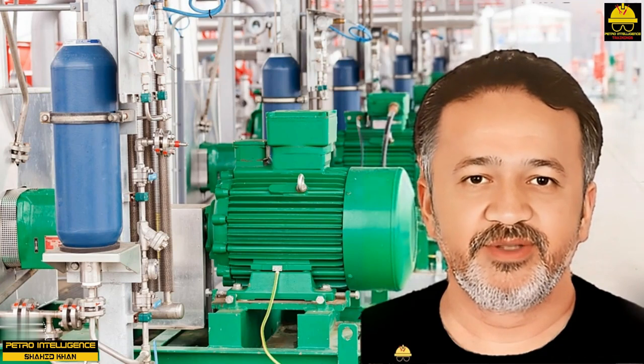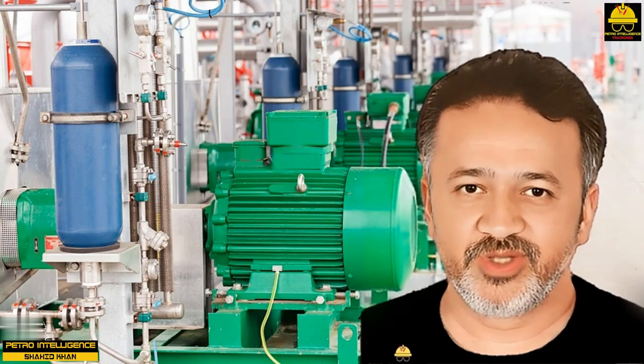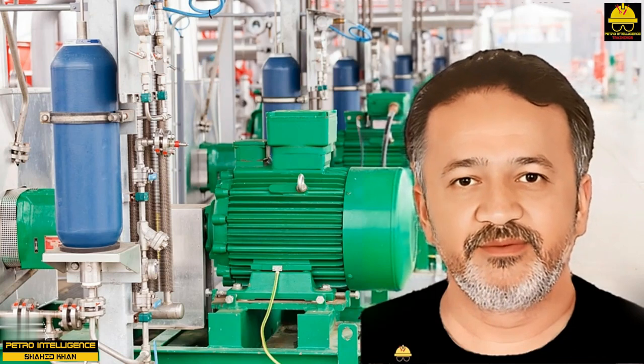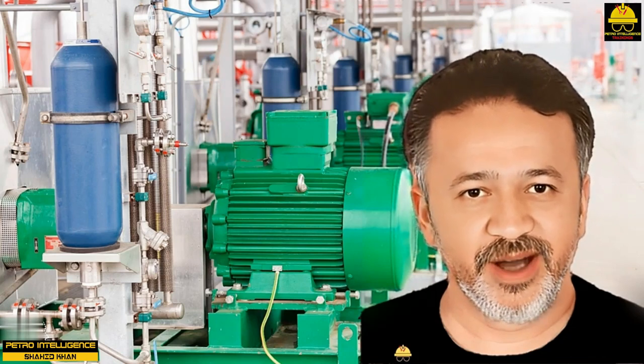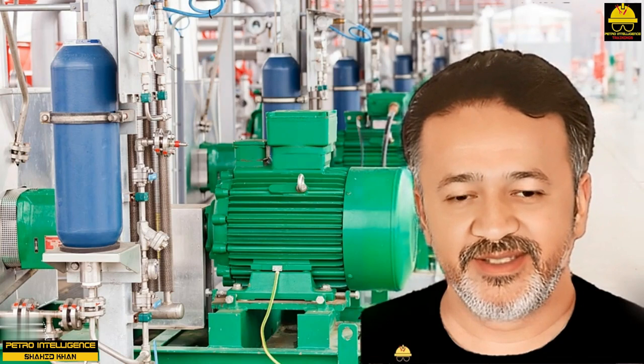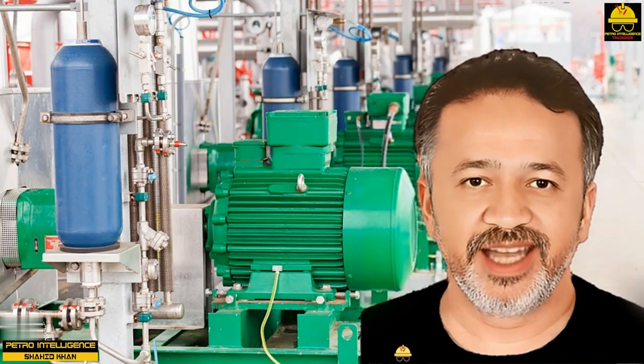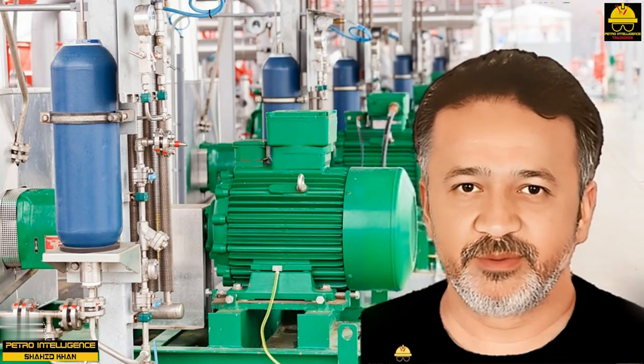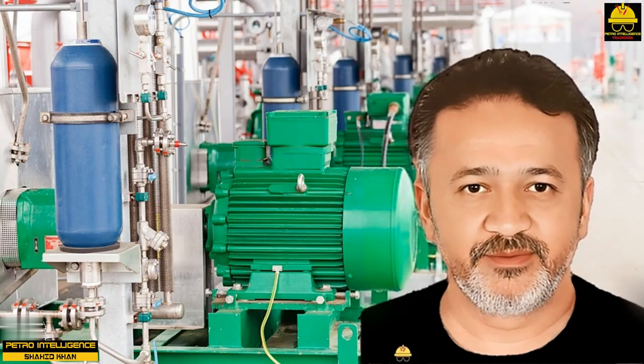Cavitation. Cavitation occurs when suction pressure drops below NPSH. At this point, the liquid vaporizes and forms gas pockets inside the pump casing. As these pockets form and collapse, the pump can be severely damaged.